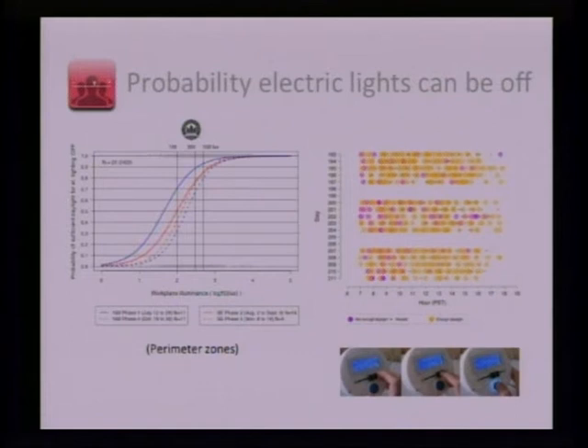So I found that even in the building when it was heavily shaded to create visual comfort, there was a kind of a canopy-like indoor lighting condition which still had low daylight levels, but it still had sufficient daylight for most of the occupants. You can see here the yellow responses over the course of the day are occupant responses indicating sufficient daylight. And so particularly for people working in the core, we shouldn't assume that they really expect the same level of daylight as those in the perimeter.